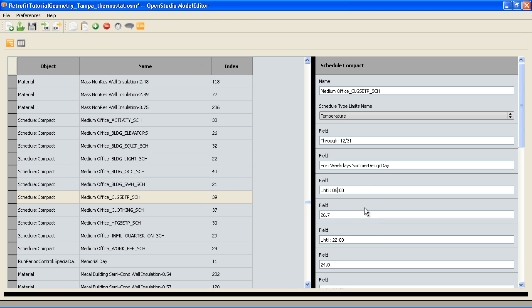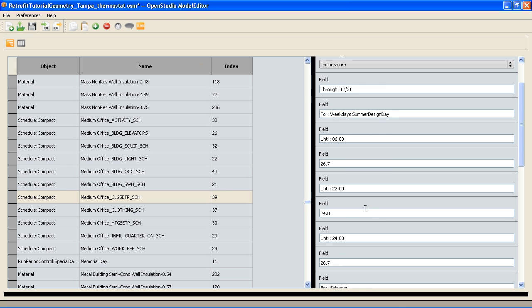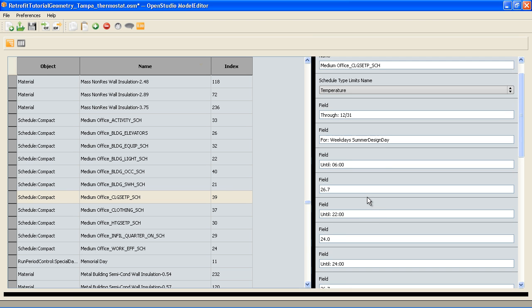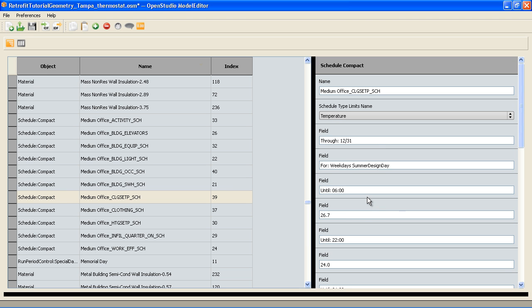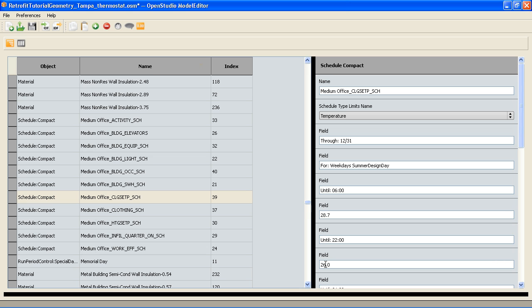We can change the times, or if we have a school that has a partial year, we can change seasonally what happens. Or I can keep all the times the same and just set this back. Right now we're in cooling, so I can set this up 2 degrees to 28 and then set this to 26. I can go through the schedule and push everything up 2 degrees across the board and then down 2 degrees for heating and see how that impacts our loads.